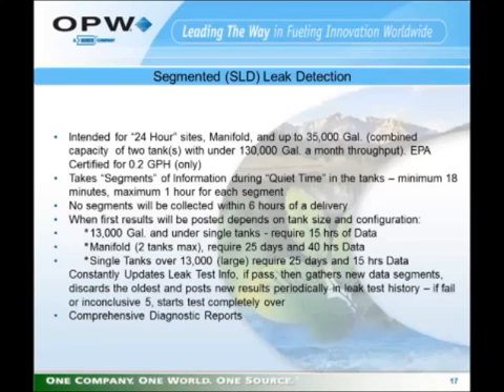The system monitors the tank similar to the continuous static test, and when it sees that the tank is idle, it will then start collecting data in segments. A segment of data, minimum size is 18 minutes, maximum size up to an hour. So if it can collect the whole 18 minutes, once the tank goes active again, it stops collecting the data and stores that segment that it collected. It will then add those segments up over a period of time to build a database for the tank and then be able to issue a test result. As with the static test, it will collect no segments within 6 hours of a delivery.